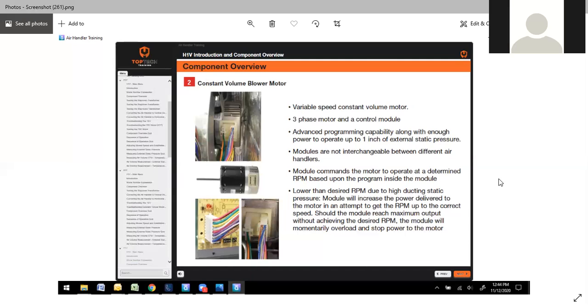If I'm selling furnaces now in the field, first thing I'm doing is a static pressure test on the duct system before I sell the job. That way I can tell ahead of time, hopefully you have a working blower motor. But if you can check that, you can say, okay, do I have a static issue? If you do, present that on the sale. Number one, you'll be different than anybody else. You may be higher, but you're going to correct a problem.